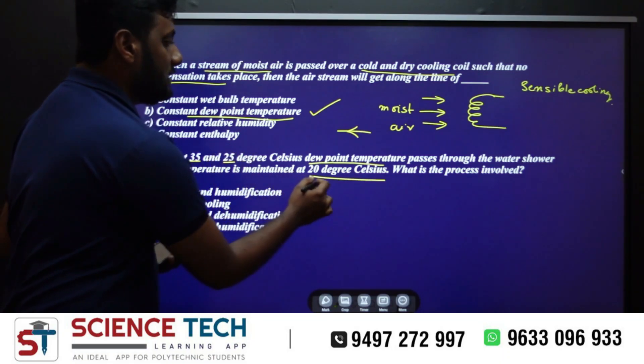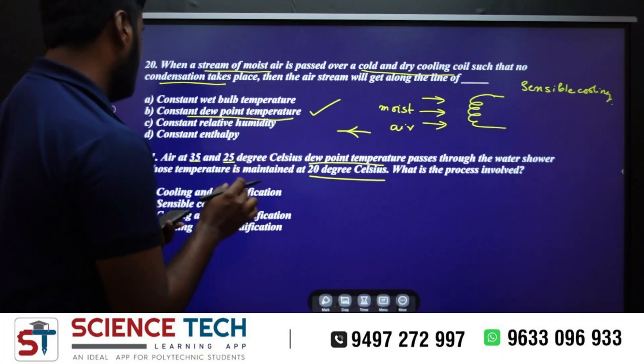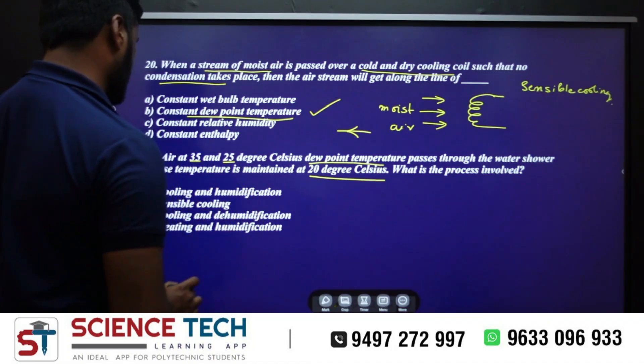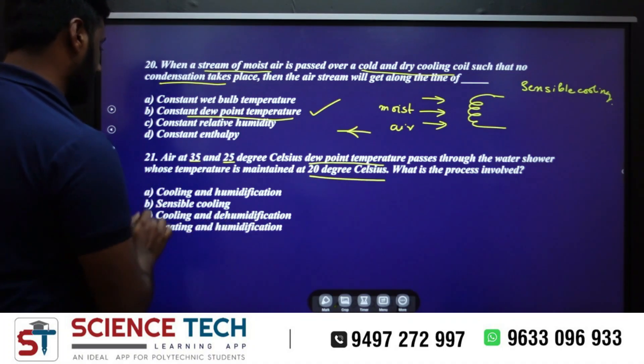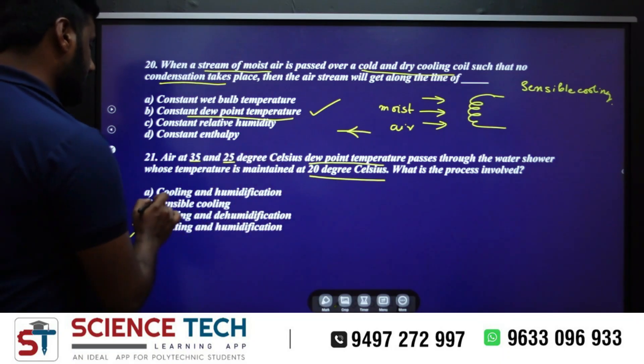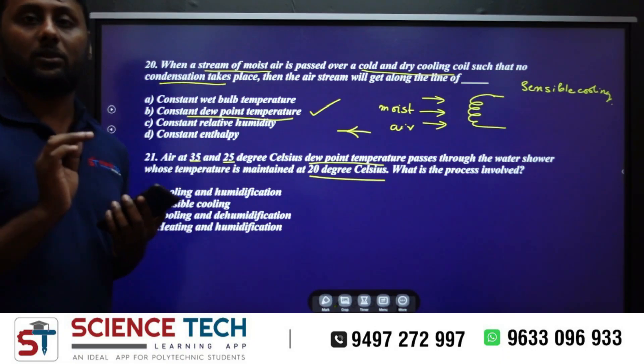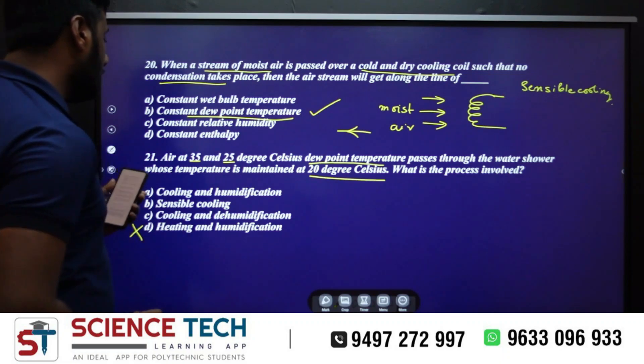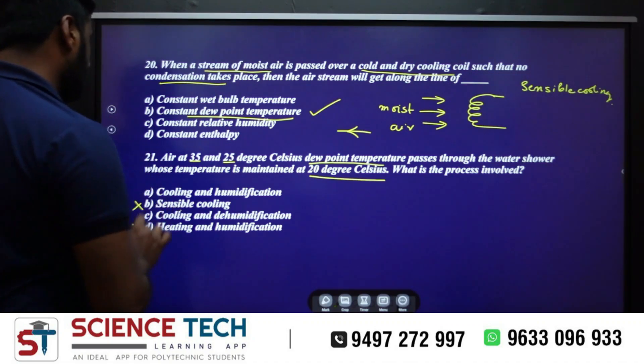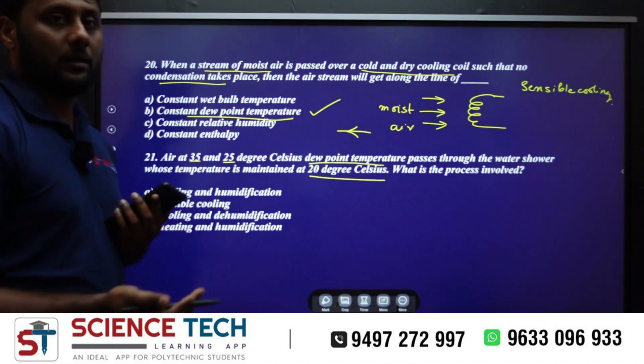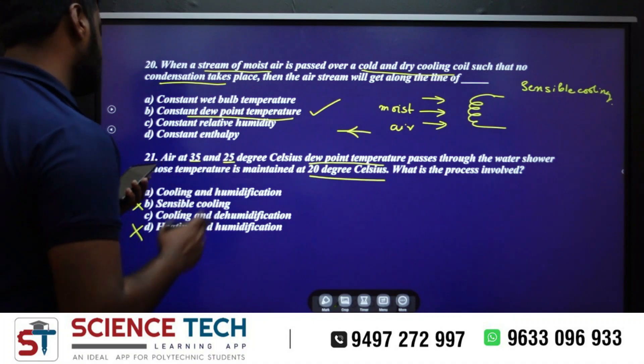The dew point temperature is 25°C and the water shower is at 20°C, which is below the dew point. So it involves cooling and something. Since the water shower temperature is below the dew point temperature, moisture will condense — so what type of cooling? Cooling and dehumidification.